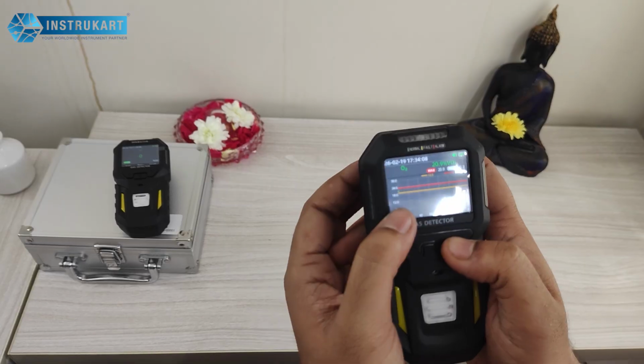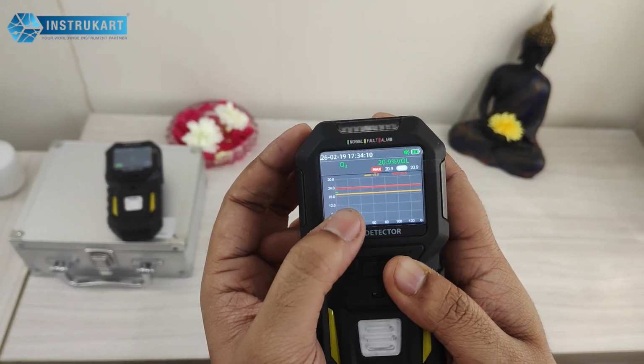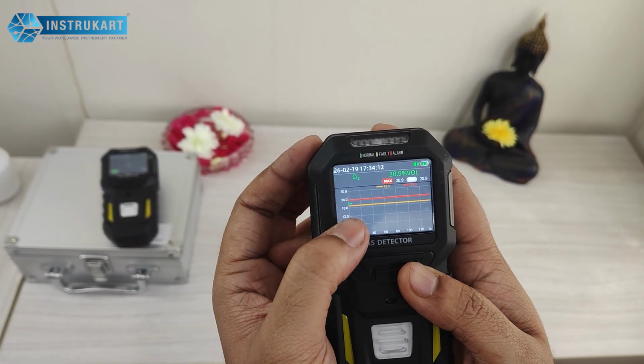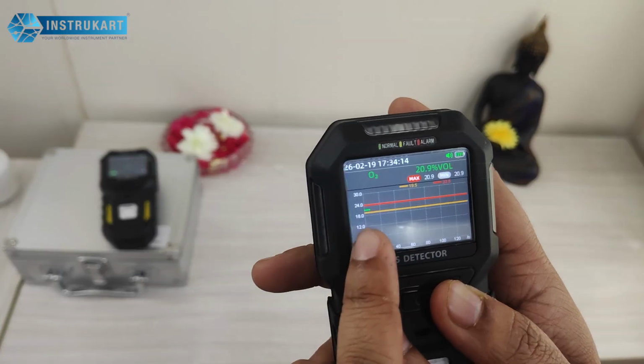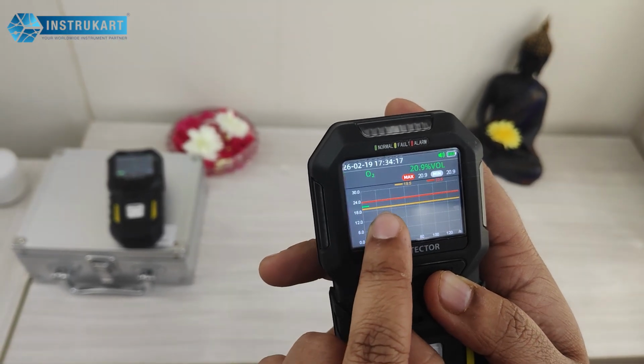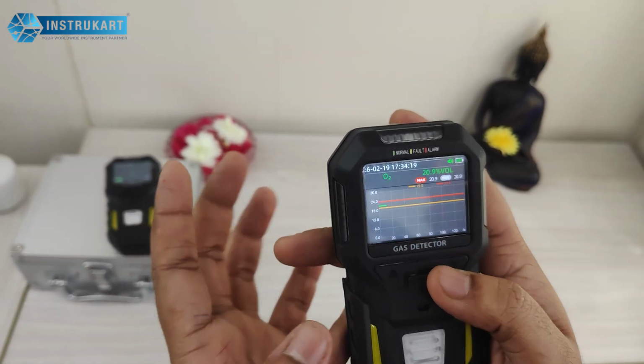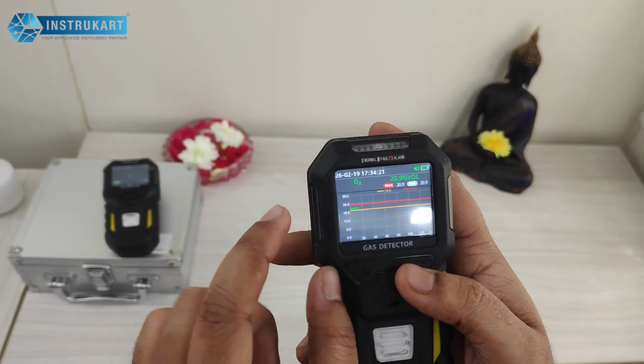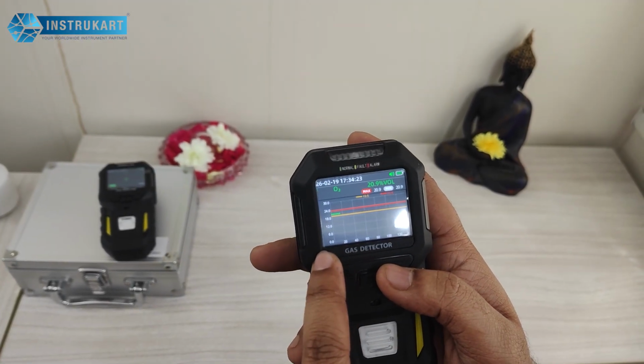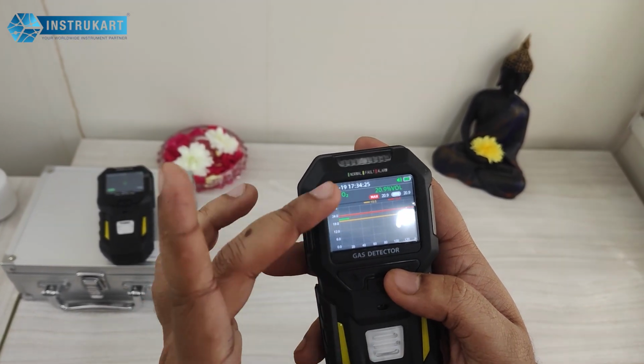The device has also got a graphical view. Here you can see the red and the yellow line. This is the maximum range and this is the minimum range. Between this, there is a green line which is showing the normal range of oxygen right now. In case of any deviation, the user will get a bar graph or a line graph somewhere here.